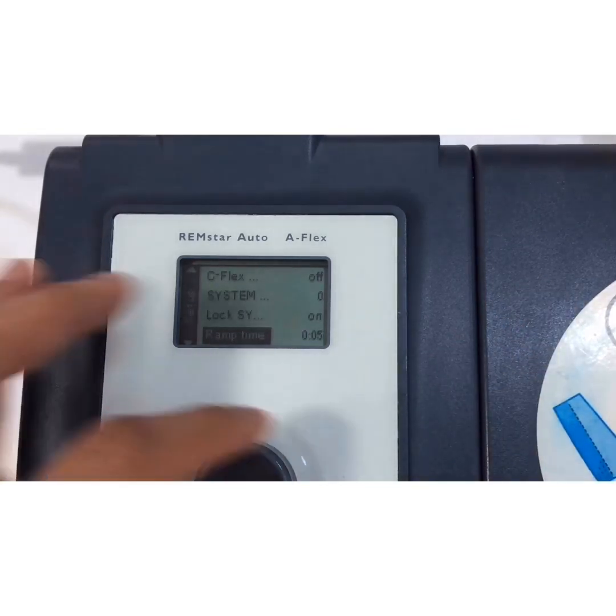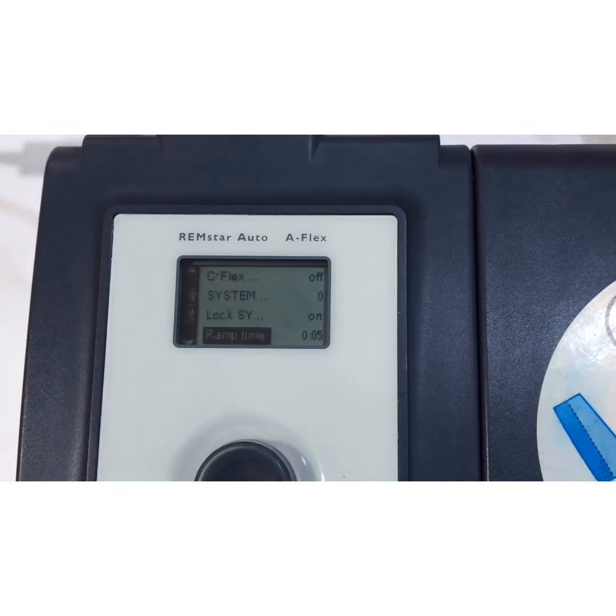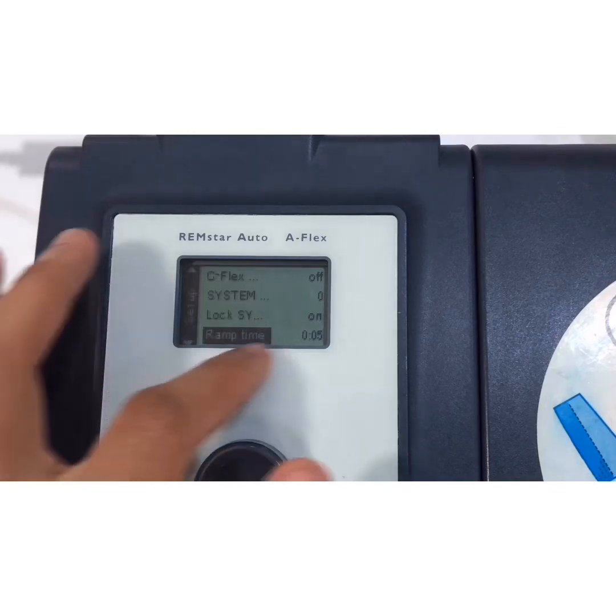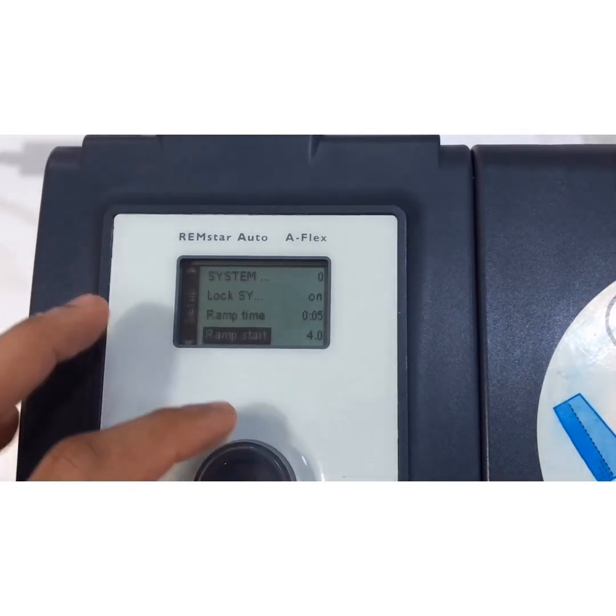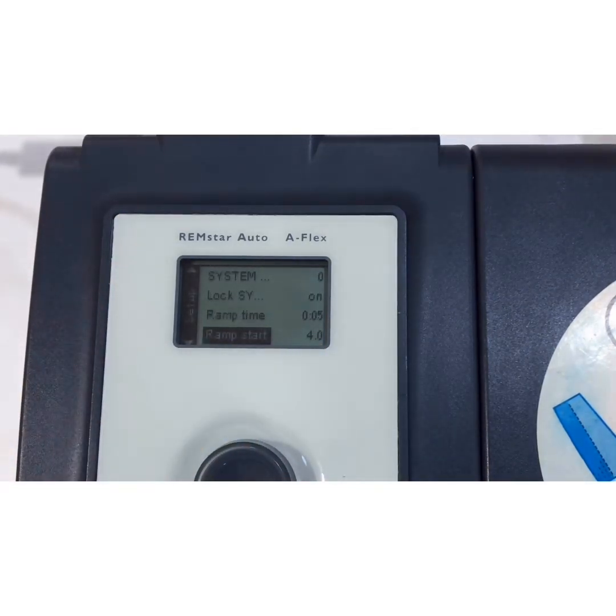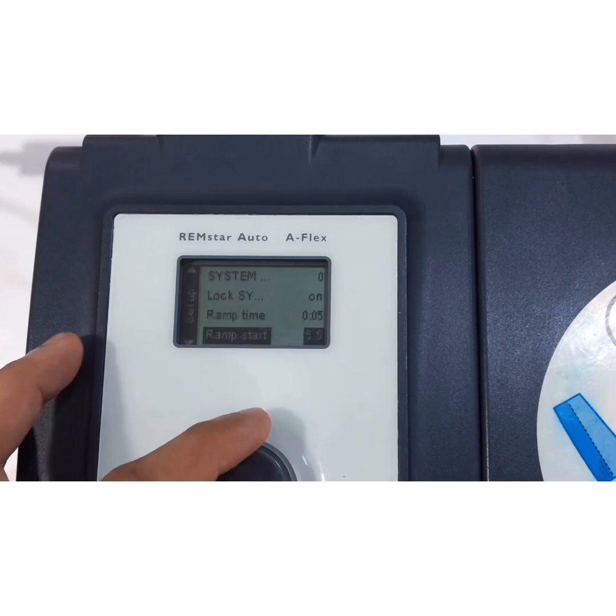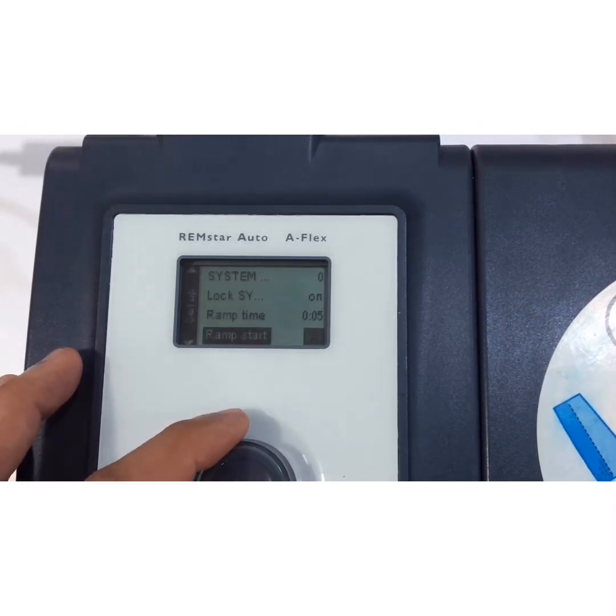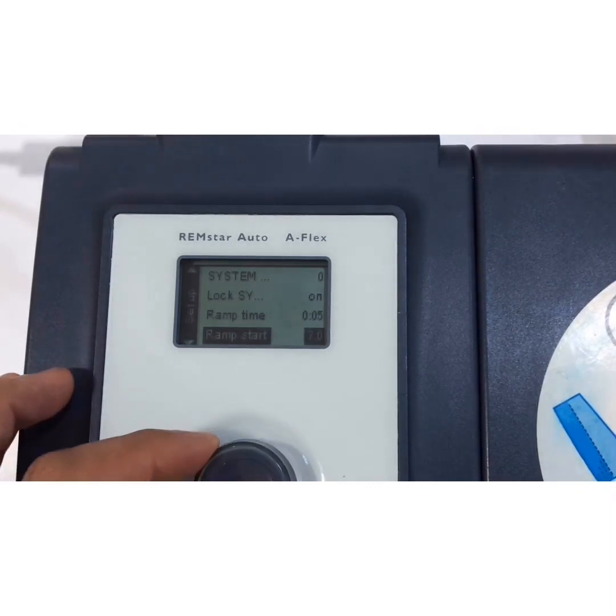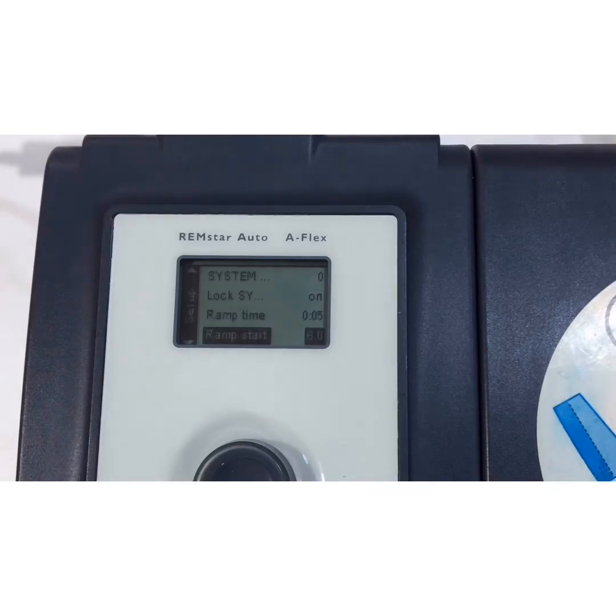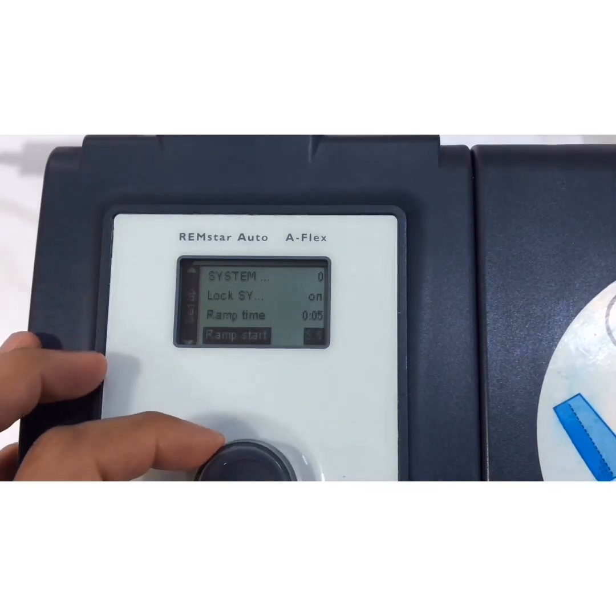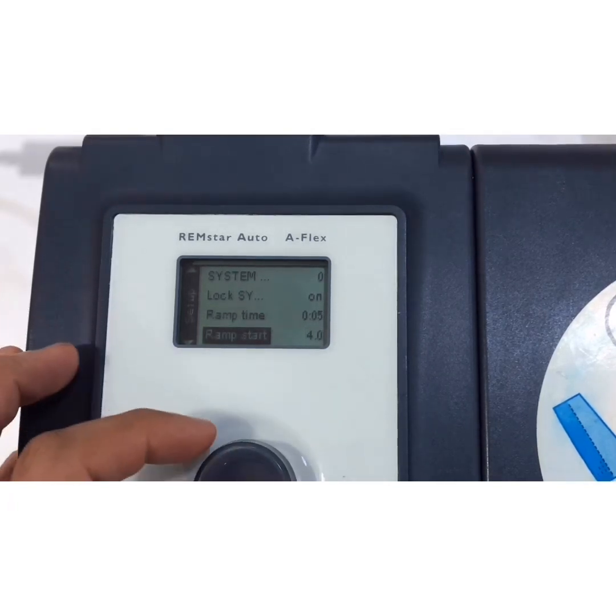Ramp time is how fast the pressure will go to the patient to the set level. For example, here it's 0.05. The ramp starts, so we have to set the ramp even if we are not going to use it. We have to set it. For example, here it's 4, but I can manipulate it. I can make it 5, I can make it 7, I can make it whichever pressure I want, but it does not necessarily have to be started with the patient. So let's imagine now we can make it 4.